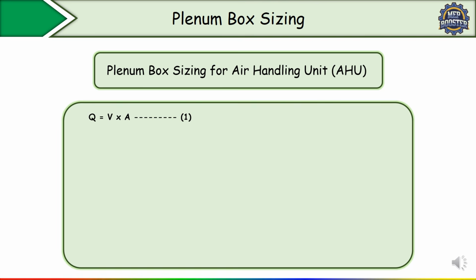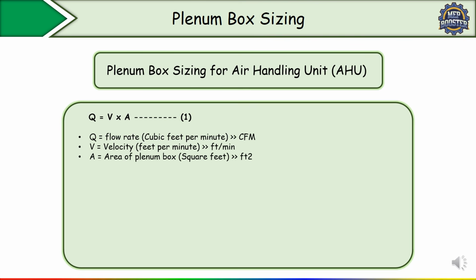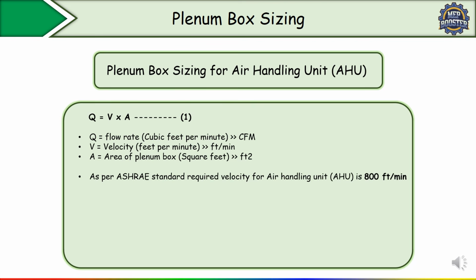First of all, here you can see the formula which we have to use is the discharge flow formula, Q is equal to VA. In this formula, Q is the flow rate in cubic feet per minute, V is the velocity in FPM, and capital A is the area of the plenum box in square feet. Correct? As per the ASHRAE standard, the required velocity for an air handling unit is 800 FPM, or you can maintain it between 800 and 1200, but normally it is better to take 800 FPM.